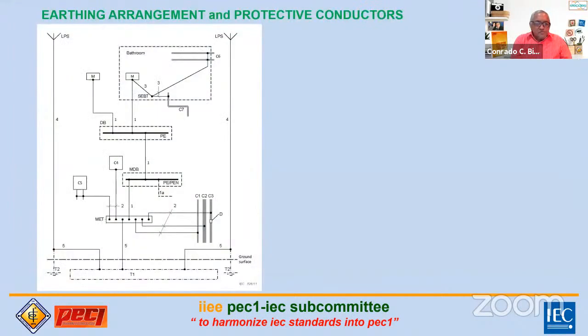Now I will show you the earthing arrangement so we can better appreciate the terminologies used. This is an example from the IEC. You can see all of this here - it's labeled as not a single line, but it is actually a single line diagram. These are all ground conductors, protective conductors. Let's see what this is.